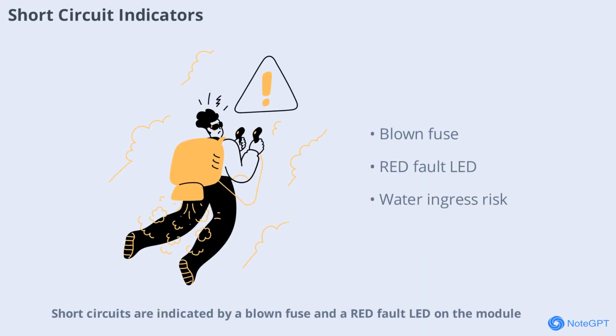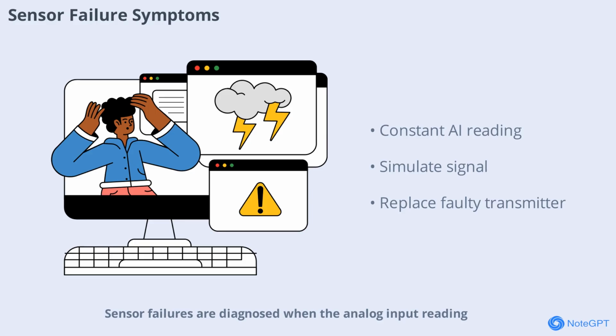Short circuits are indicated by a blown fuse and a red fault LED on the module. They are often caused by water ingress or damaged cable insulation. Detecting and addressing short circuits is vital for preventing equipment damage and ensuring system safety. Sensor failures are diagnosed when the analog input reading is stuck at a constant value regardless of process changes. Confirm this by simulating a signal. If the PLC reads the simulator correctly, the transmitter is dead. Identifying sensor failures ensures that faulty devices are replaced promptly, maintaining system accuracy.